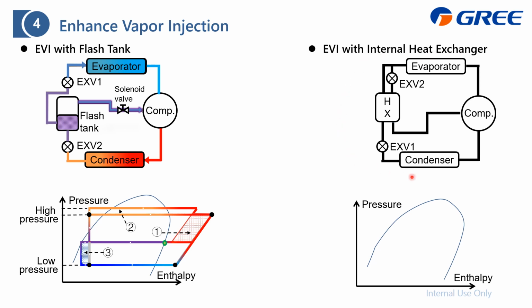And from this system diagram, we also have the compressor, condenser, but this time only one metering device for the metering process. And this is the internal heat exchanger, and this is the evaporator. And also another metering device like the EXV to control how much amount we need to inject for the compressor. First of all, I will analyze how the refrigerant flows inside this diagram. And also from the compressor it is already the high pressure and temperature vapor. Then we send this vapor to the condenser to release heat.